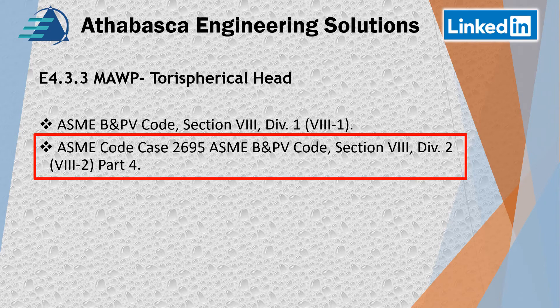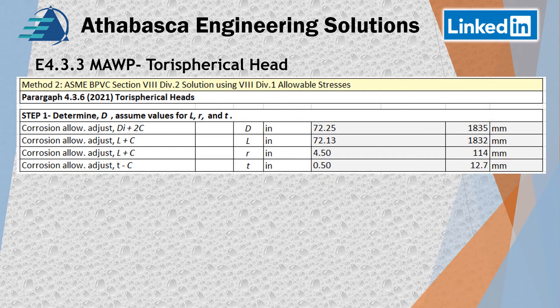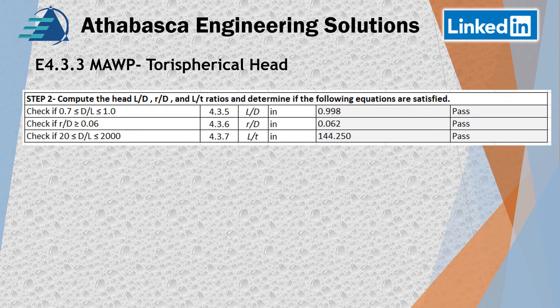We start off with the traditional setup — taking the adjustments for the corrosion allowances. Then in step two we take the ratios and do some checks. We have to make sure we're following the required ratios per 4.3.5. L over D has to be between the specified values — pass. R over D has to be greater than the limit — pass. If you're doing the code case calculation, we'll do a future presentation where we take a full Division 2 calculation and look at it that way.